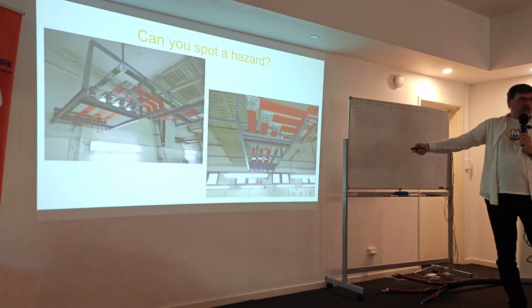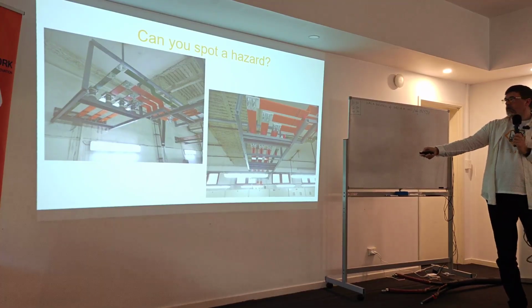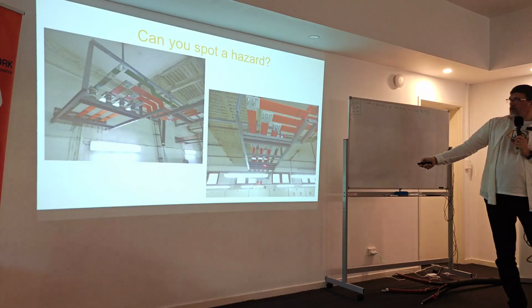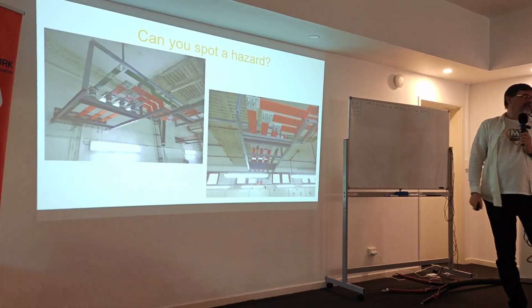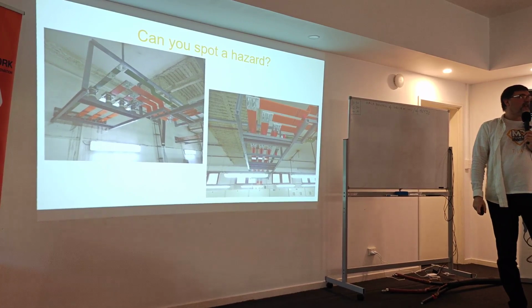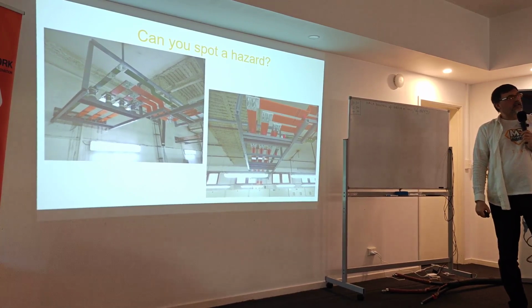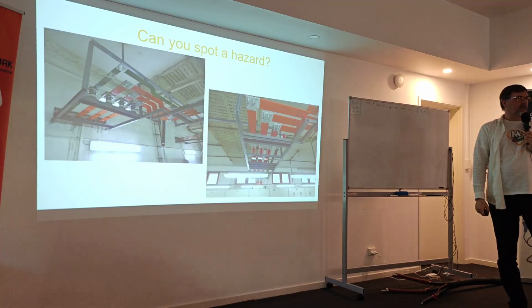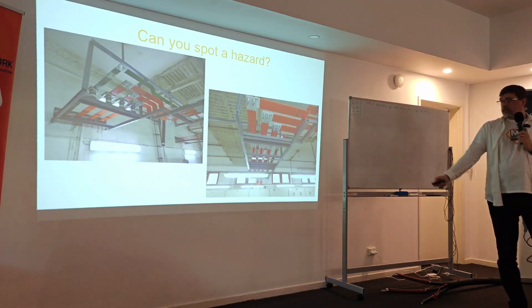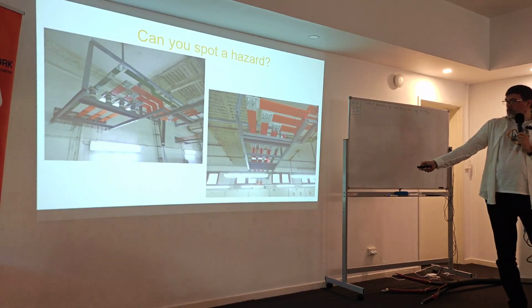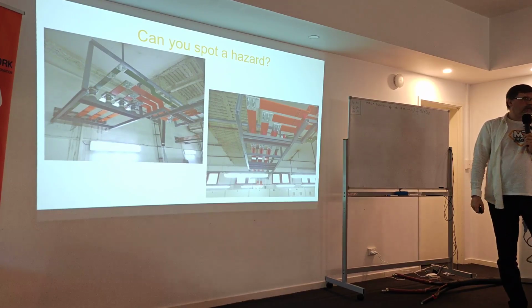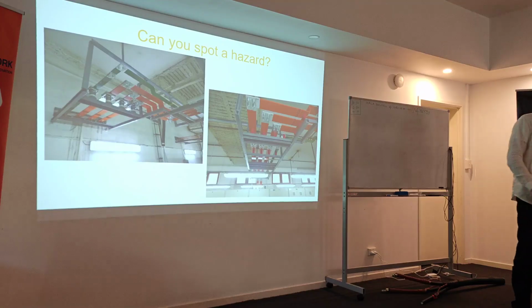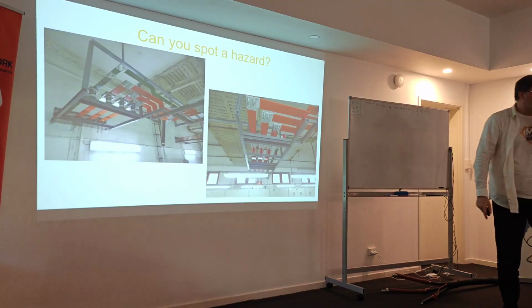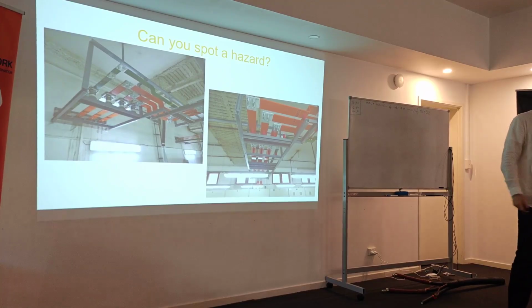So we all see the problem is shock hazard and arc flash. Yeah? They didn't know what arc flash is at that point. What procedure you write to change this light? If someone will just tell you, I go to change light in the substation, doesn't sound like a problem, yeah? And this will be treated almost like the working, because this is the worst location. Almost like live work, but technically it will be treated as a dangerous condition, which you need to go over the full permit to work just because you want to change the light, or this one, for example. And imagine someone brings the aluminum ladder.